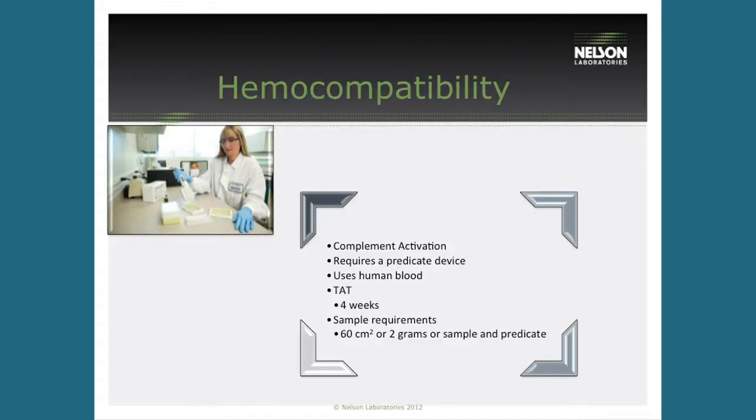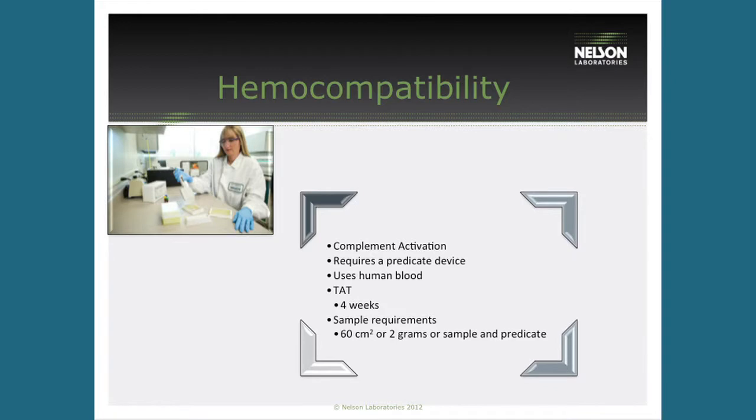The next test I want to run over very quickly is the complement activation test. Historically, complement activation was only run on devices with large surface area — like blood filters, long tubes, and tubing sets that contact a lot of blood. The historical thought was you needed a lot of surface area to react to the complement system. The FDA doesn't necessarily agree with this, and in fact in the last couple of years they've been requiring every device that contacts circulating blood to do a complement activation test.